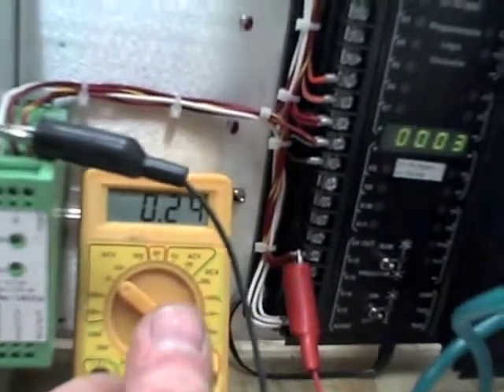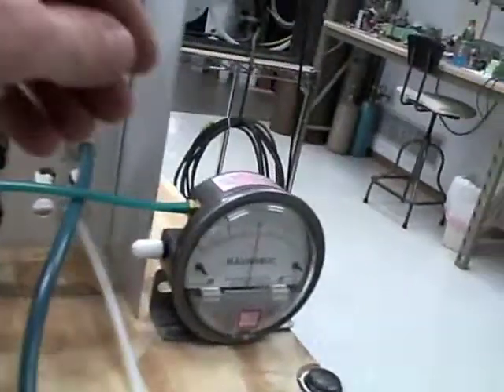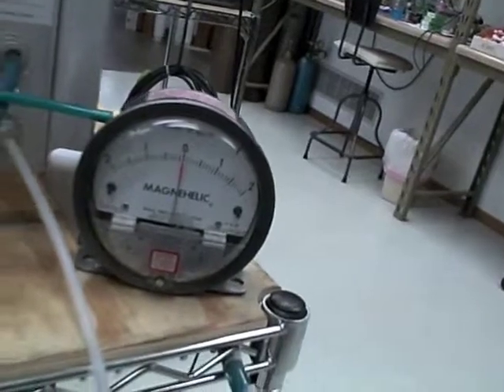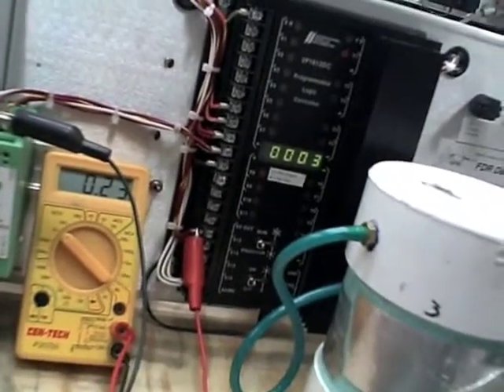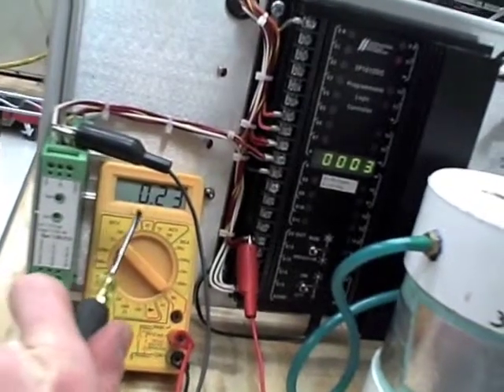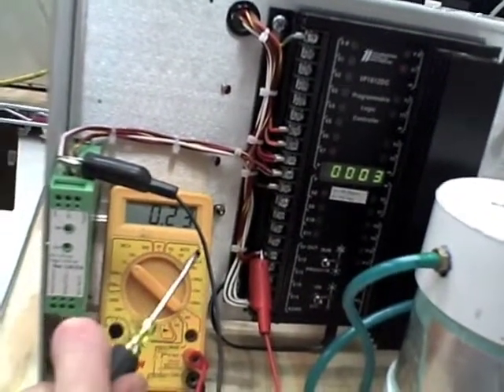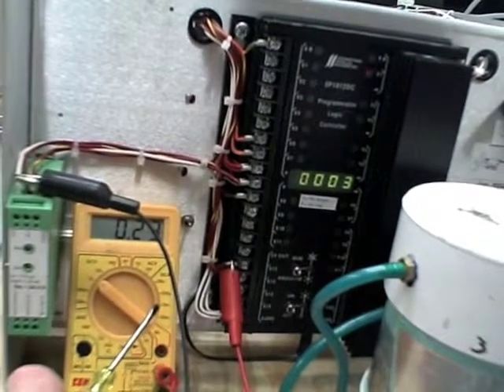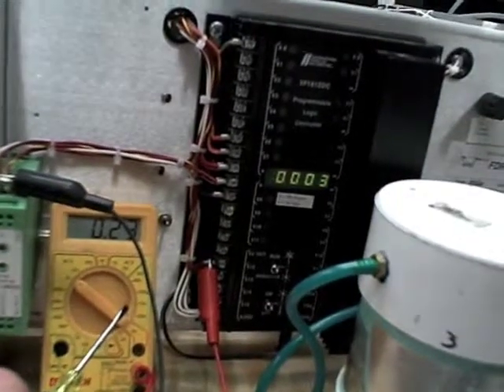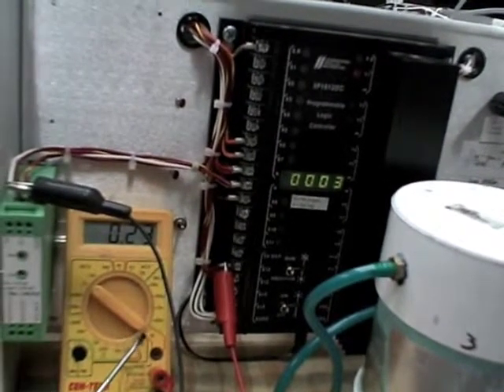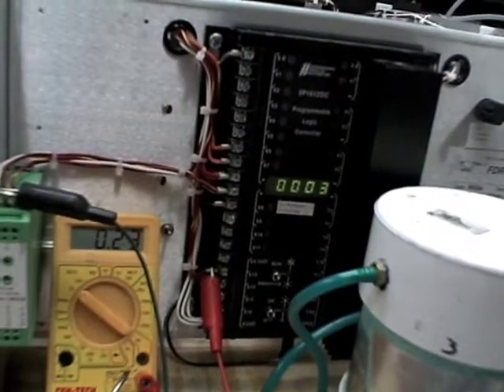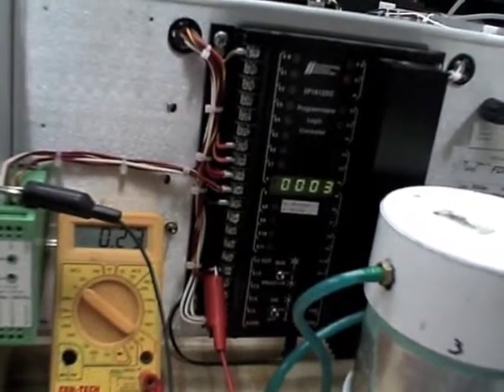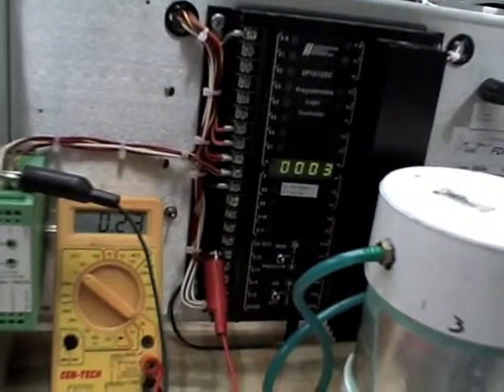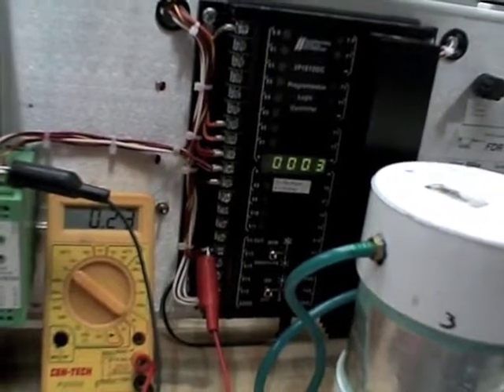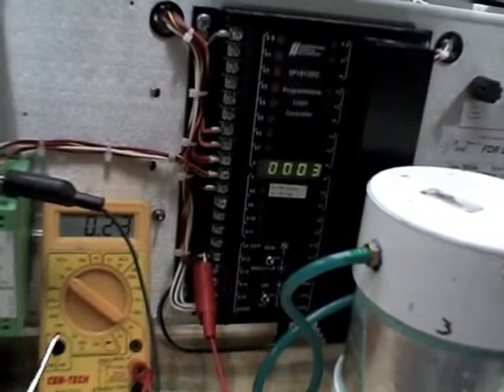And again, my lance is still in the test jug, my Magnehelic is still reading 0 because we haven't started the machine yet. And then as I start the machine, I'm going to take my screwdriver again and turn up the gain screw to adjust the calibration till the voltmeter reads 5 volts. And then if we look on the front of the machine, you'll notice that the meter on the front of the machine should say 100%. The meter on the front of the machine is a 0 to 5 voltmeter, and so 100% will be 5 volts back here. And so the front meter is mainly for the operator to see that the machine is working right. They are getting 100% fill or the 5 volt setting anyway, fill.